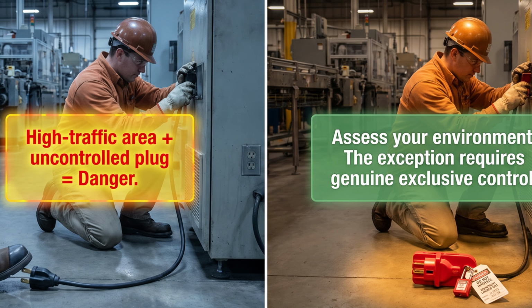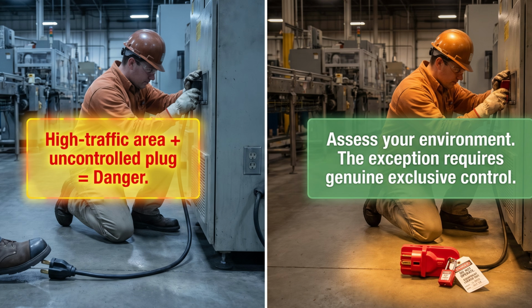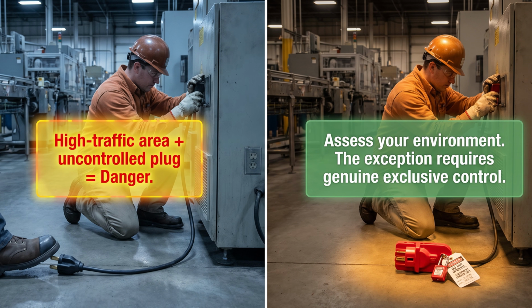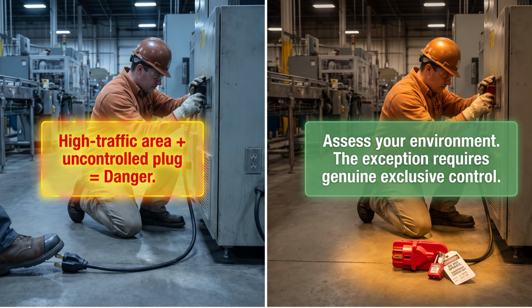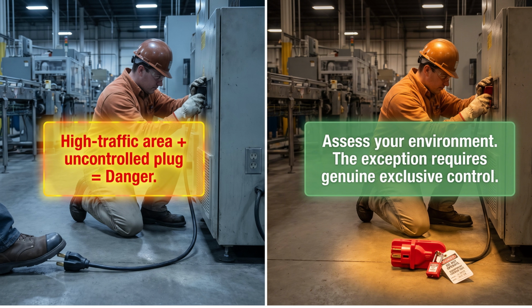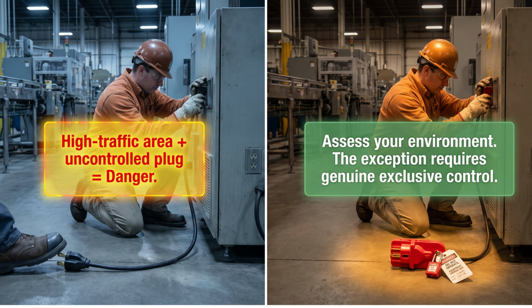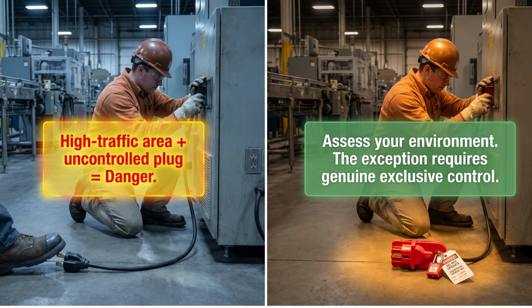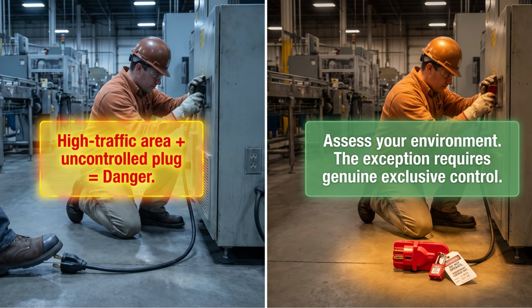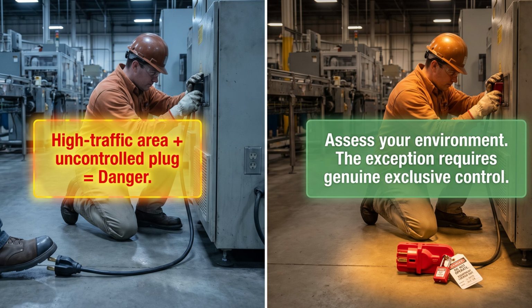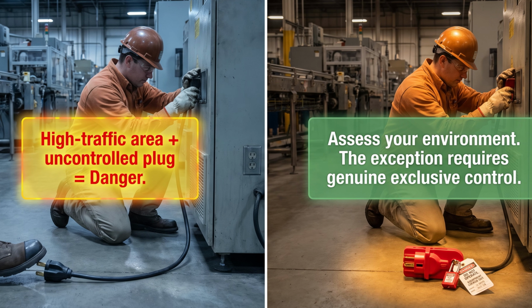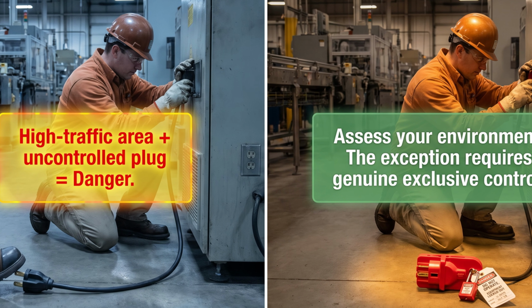The cord and plug exception only provides protection when your control of the plug is genuinely exclusive and uninterrupted. High traffic areas, multiple workers in the same space, shift changes, and shared equipment all increase the risk that exclusive control is compromised. If there is any realistic scenario where someone could plug the equipment back in before your work is complete, the exception doesn't provide adequate protection, and a plug lockout device is required.